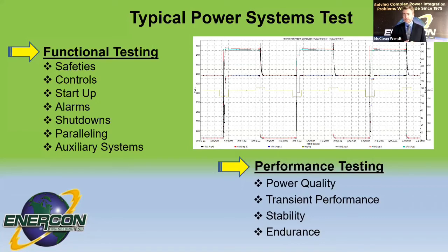And whatever the load profile that we go through is going to be governed by the customer and what their power needs are, including their requirements of what the overshoot is for frequency and undershoot for voltage. All of those will be determined by the customer. And then there's voltage stability and frequency stability, to make sure that if you're running over a period of time, your voltage and frequency are not drifting away from the nominal rated value. And then finally, endurance tests can be run just to shake out any of the bugs or early problems that you might have on a system to give better reliability.